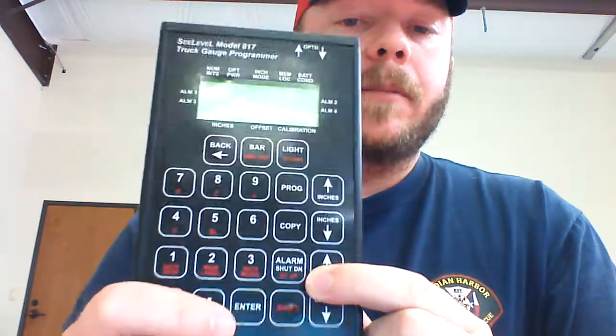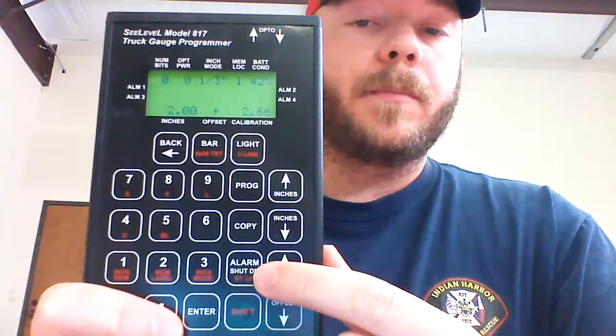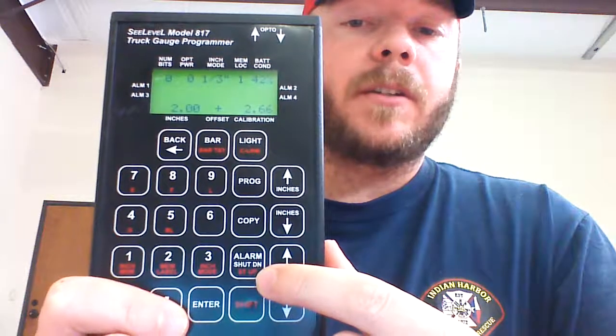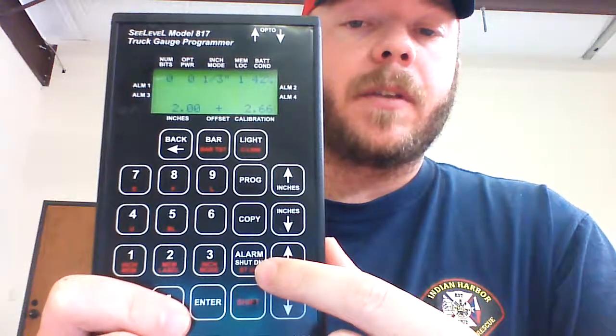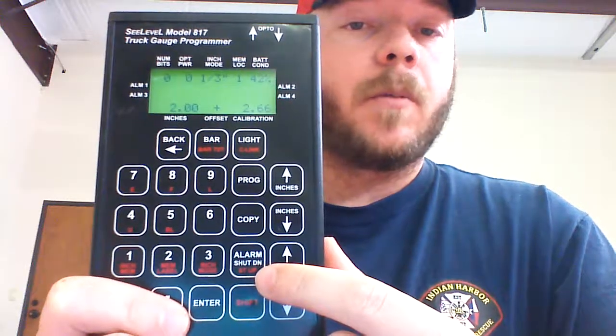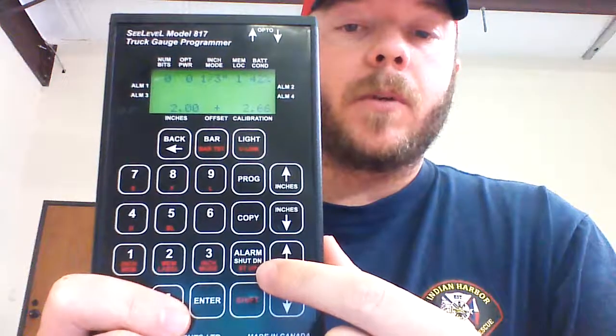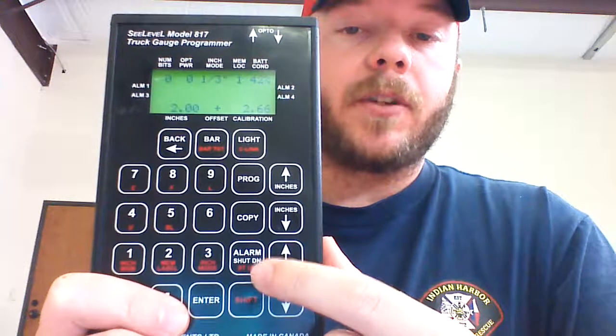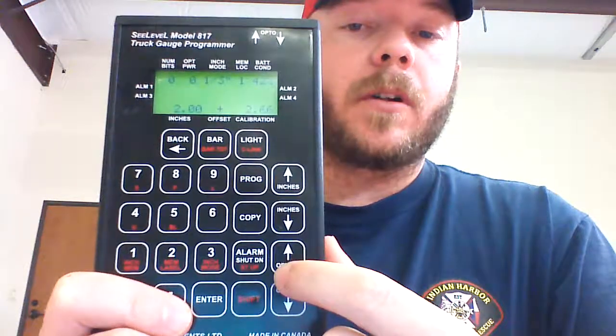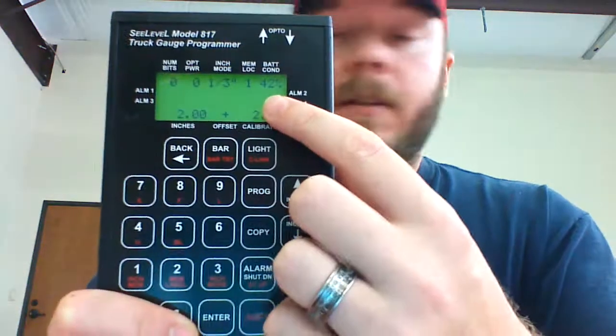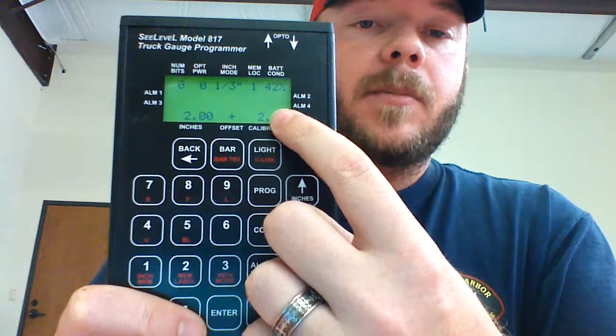The alarm shutdown button in white there is the button we're going to use to store alarms. One thing to note, the red letter secondary menu there is the setup function. We're not going to use the setup function. We will rarely ever use that. So when we store an alarm into shutdown, the calibration will show up here. The alarm setting will show up with the letters SD for shutdown beside it. So when we copy out a display, we want to make sure the alarms are stored in shutdown.